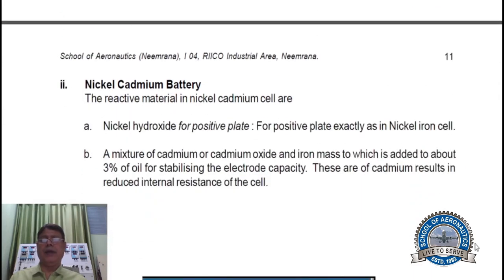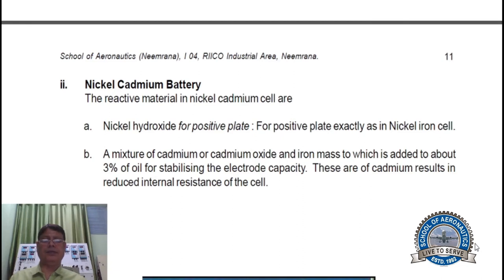Nickel Cadmium battery. The active materials in nickel cadmium battery cells are: nickel hydroxide for the positive plate, exactly as in the nickel iron cell. For the negative plate, a mixture of cadmium or cadmium oxide and iron mass, to which about 3% of oil is added for stabilizing the electrode capacity. Cadmium results in reduced internal resistance of the cell.